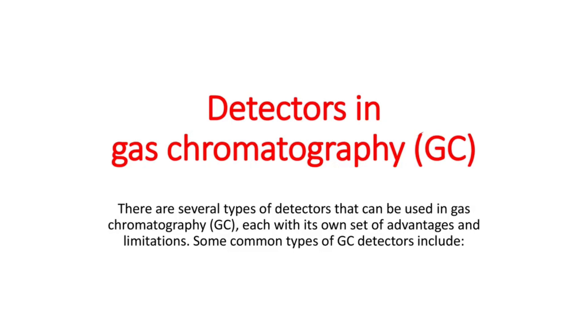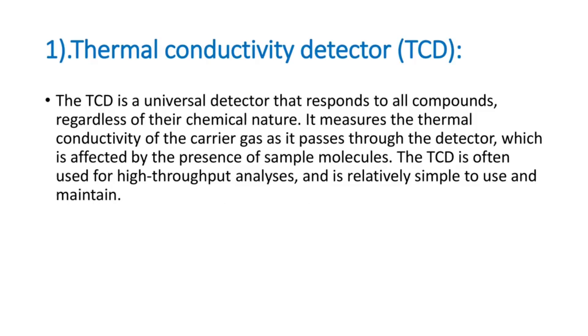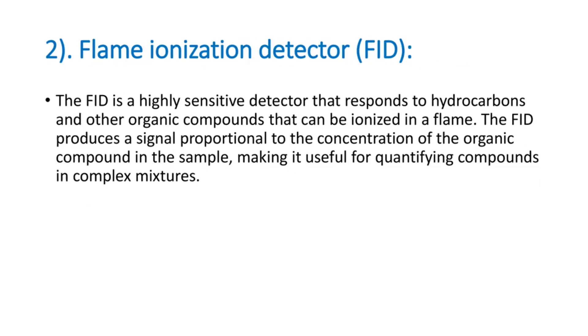First, a very important one: TCD, means thermal conductivity detector. The TCD is a universal detector that responds to all compounds regardless of their chemical nature. It measures the thermal conductivity of the carrier gas as it passes through the detector, which is affected by the presence of sample molecules. The TCD is often used for high throughput analysis and is relatively simple to use.